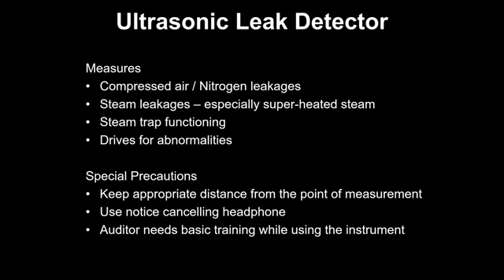It can also be used for steam leakages, especially superheated, because superheated steam leakage is not visible. It can also be used for steam trap functioning, because when the steam trap discharges, there's a peculiar sound. If that sound is picked up by the ultrasonic meter, we can use it for trap functioning. One needs to be slightly careful when using a float type trap, because some of those traps are continuously discharging and the reading may not be correct.